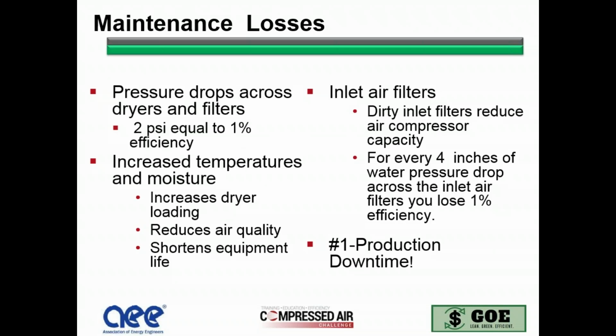Maintenance is always a necessary evil. I spent a lot of my career on the maintenance side, and it's an important part. Again, we talked about the pressure drops for lowering pressure. The same is true for the actual pressure drops across the filters, dryers, and any component in the system. Again, that same 2 PSI equals 1% efficiency relates to those pressure drops.